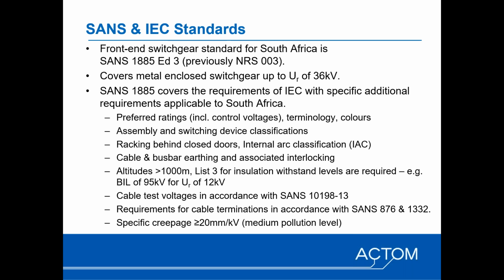And then it goes on to provide other requirements relevant to the industry, such as cable test voltages, requirements for cable terminations and dimensions to ensure that 3-core cables can be terminated without the need for drop-down boxes or trifurcating kits. And then something else which people may not be aware of is the requirement for 20 mm per kV creepage distance for air-insulated switchgear. And Johan will talk about some of those technical issues later when he covers some of the details of this presentation.